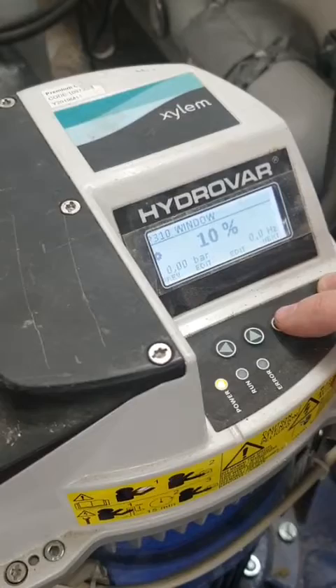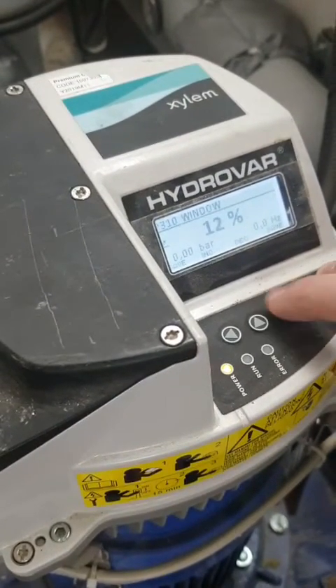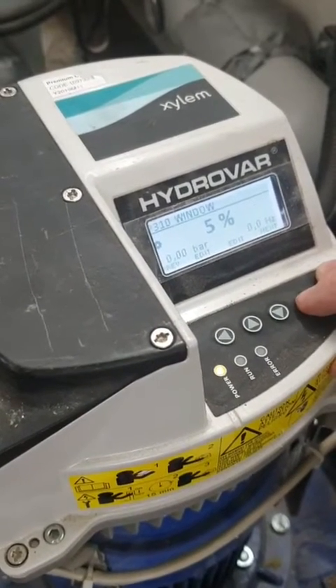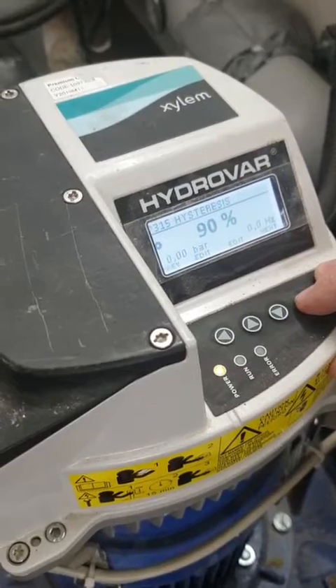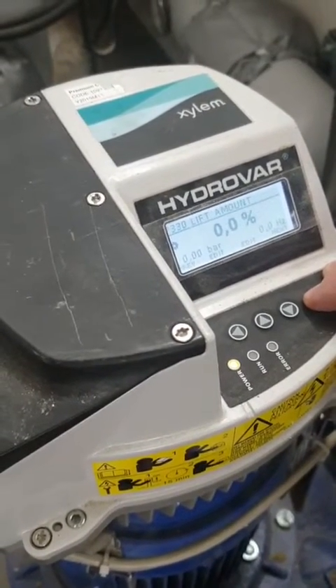Now that's our window. Because we're running on a closed loop we like to run at 5 so that we don't have a lot of pressure fluctuation. Hysteresis has come from 80 to 90, and we carry on through.